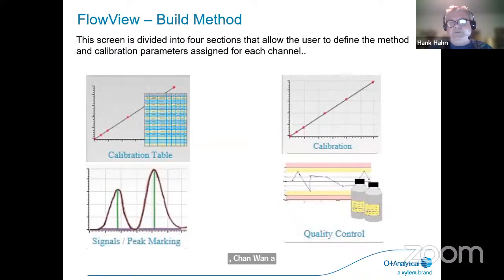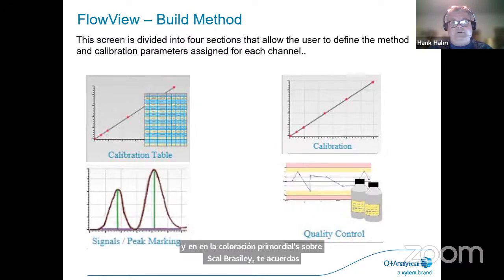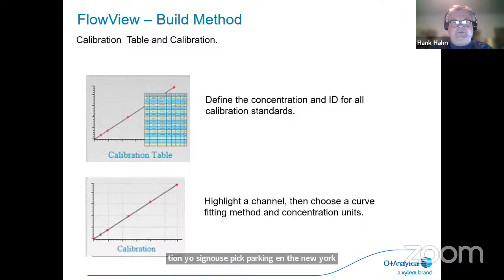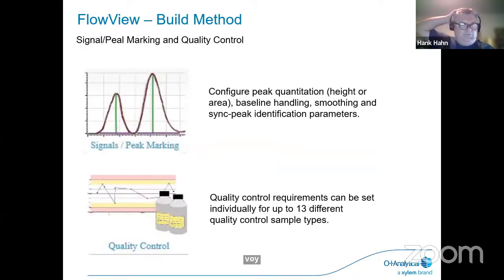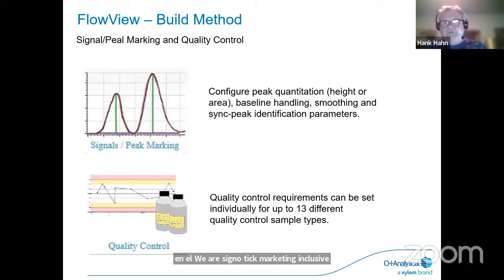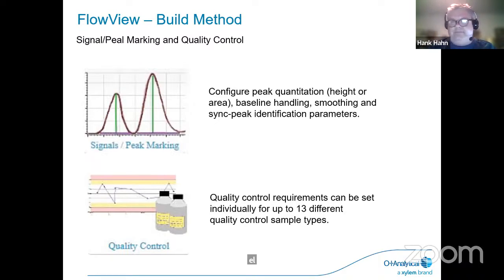In your FlowView build method, here is where it's divided into 4 sections that allows you to define the method and the calibration parameters assigned for each channel. So there's calibration table, the actual calibration, your signals and peak marking, and then your quality control. You can define the concentration and ID for all the calibration standards in the calibration table. And you can highlight a channel, then choose a curve fitting method and concentration units in the calibration. With our signal, peak marking, and quality control, you can configure peak quantification, height and area, baseline, smoothing, and sync peak identification parameters. In the quality control, we have the ability to set up 13 different quality control sample types.